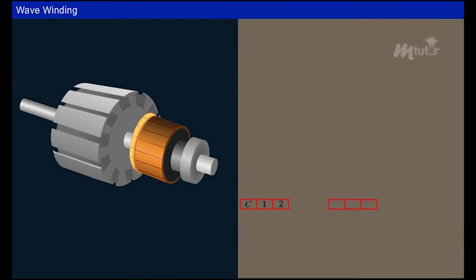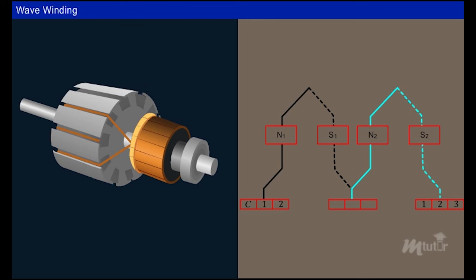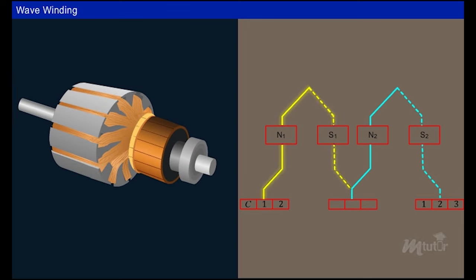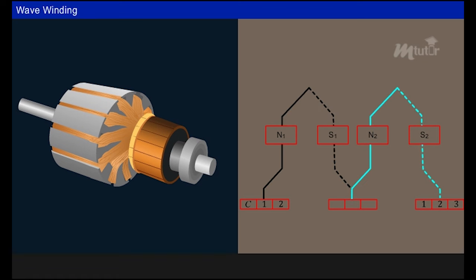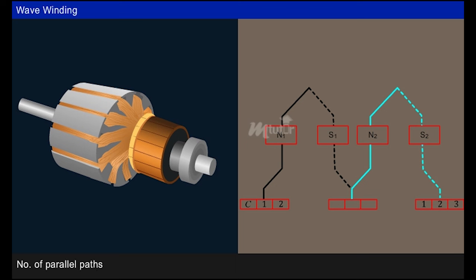In wave winding, the completing end of a coil is connected to the starting end of another coil under a different pole pair, moving ahead and avoiding overlapping. This process continues for the remaining coils. The appearance of this coil winding resembles a wave, hence the name wave winding. Here, regardless of the number of poles, the number of parallel paths is always equal to two.